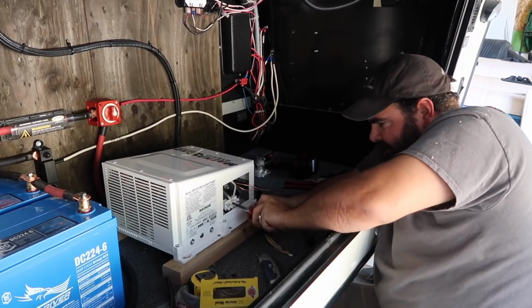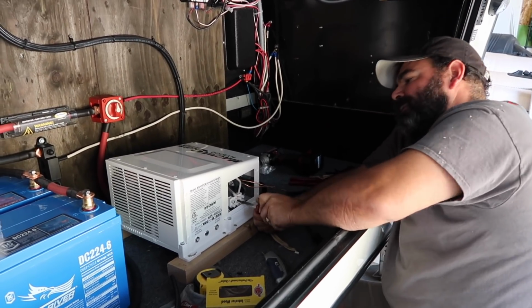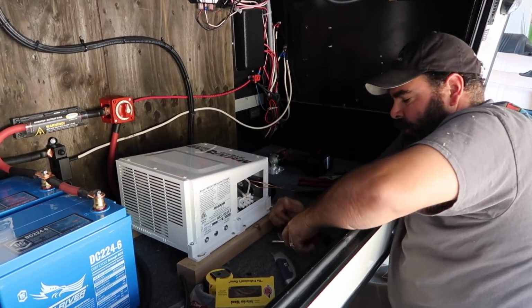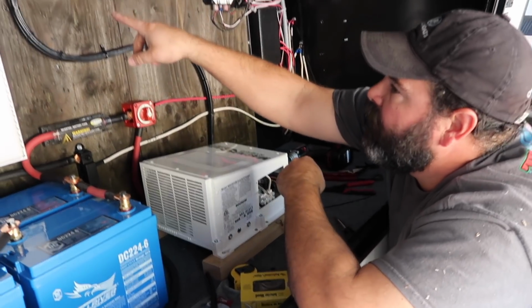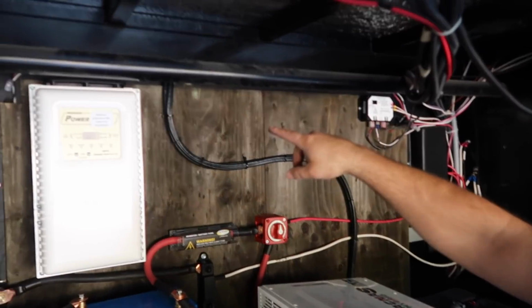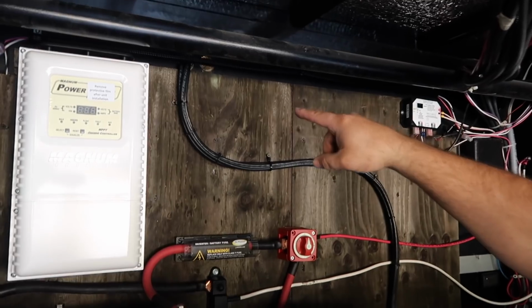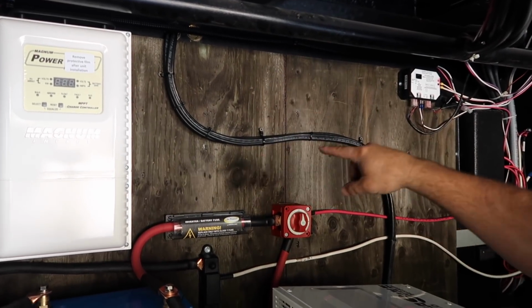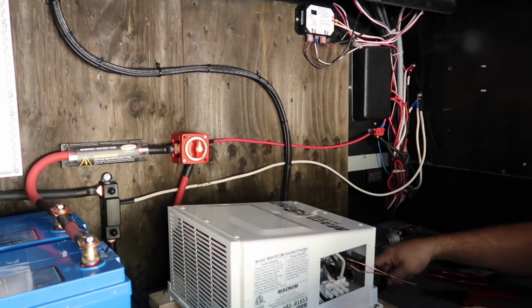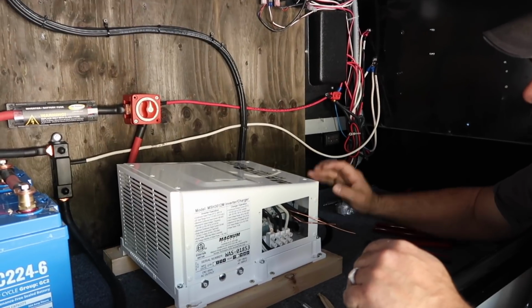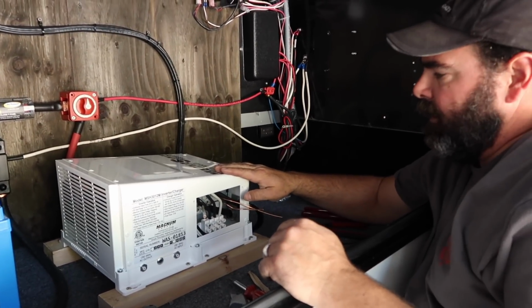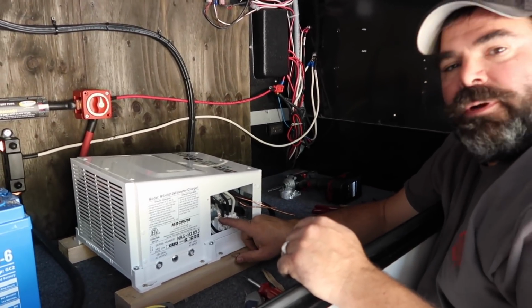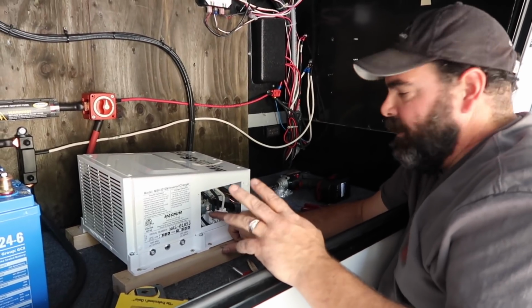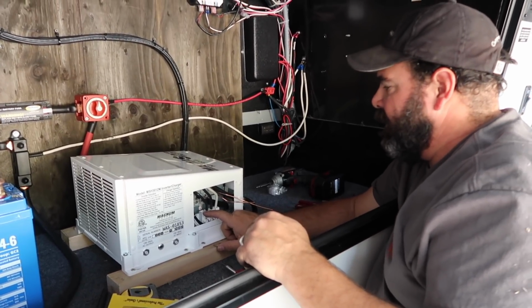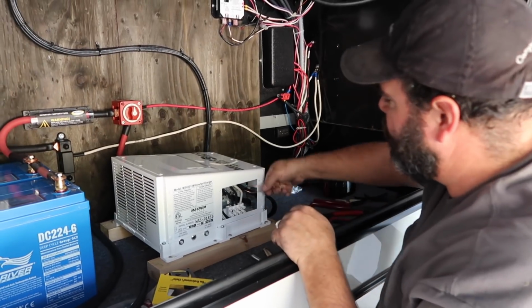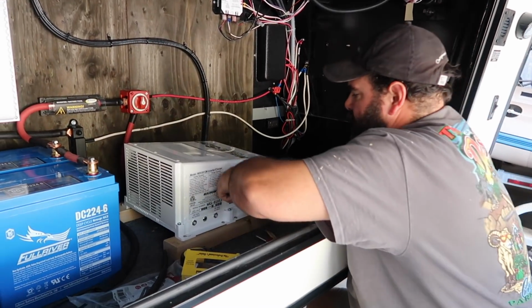Okay, so just finishing up the connections. You can see the wires over here - I ran them from the main panel and the sub panel. They come down along this wall and into the AC junction box on the inverter. Right now I'm just wiring up the neutral wire for the sub panel. Once that's done, this will basically be complete here. They've got to tie the neutrals together, of course.